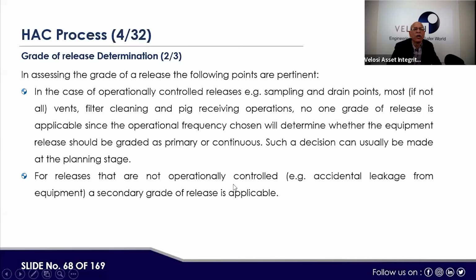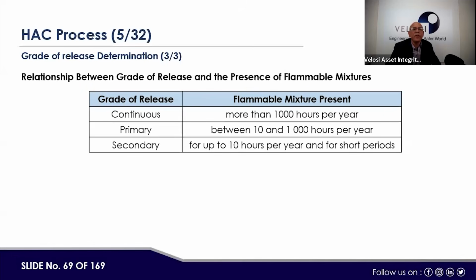And secondary means we have to go to level 2 or zone 2. Here, the definition is also given in the standard: continuous is more than 1,000 hours per year. If the hydrocarbon is available more than 1,000 hours per year. Remember, there are 8,000 hours in one year, so 1,000 means about one eighth of the year. If hydrocarbon is available, that will be called continuous. Then 10 to 1,000 hours per year is primary. This is zone 0 as per IP-15. Then zone 1 is primary, and secondary is up to 10 hours. This is basically called zone 2.